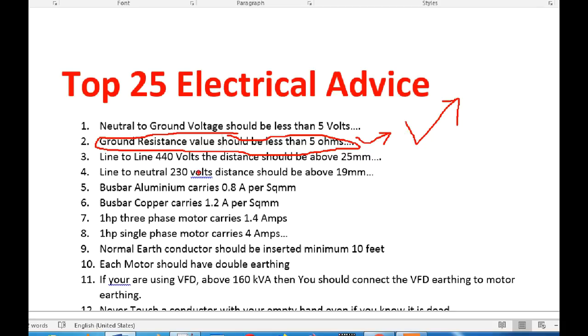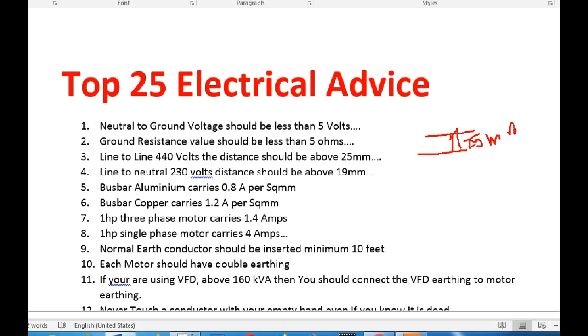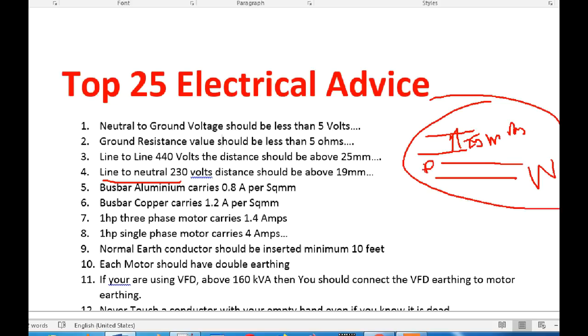Let's look at line to line. If you use a 440 volt system, if you have a distance between a line and a phase, it will be 25mm — that is the standard for a panel manufacturer. Line to neutral: if you have a phase, it will be 19mm minimum. So 19mm is the standard. You will check that.